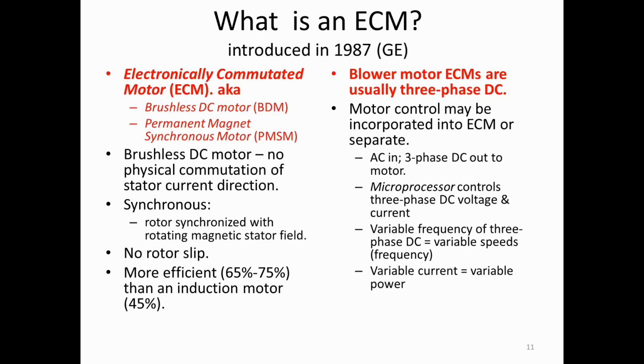It's actually a somewhat old idea. General Electric developed ECMs in 1987. It stands for electronically commutated motors. For those of you that are familiar with induction motors and earlier motors, it's a brushless DC motor. It's a permanent magnet synchronous motor. By a brushless DC motor, I mean there is no physical commutation of the direction of the current in the stator. By synchronous, I mean the rotor is synchronized with a rotating magnetic stator field, and I'm going to present graphical examples of that. There's no rotor slip, and it's more efficient, probably 65 to 75% efficiency, than an induction motor, which, based on what I've read, has about 45% efficiency.